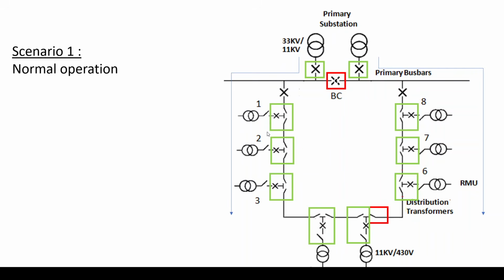What's happening here? Whatever is clouded with green has power and it is closed. The incomers are closed. Whatever is having green color is closed. So in this case, I'm feeding the power from this feeder. As you see, power goes on like that, goes on like that, reaches here, and then at a certain point in my network, I'm opening one terminal of the RMU. So this feeder stops here. It's connected from this. And the second part of the ring is connected from here. Since this bus coupler is open, no power is flowing here and no power is flowing here. So this one is providing power to the second half of the ring circuit. So you see it's reaching up to here and this terminal of the RMU is open. Therefore, my loads, my 11 kV network is up and running.